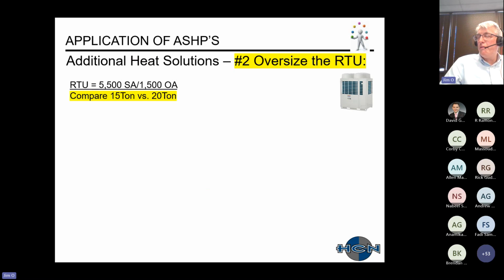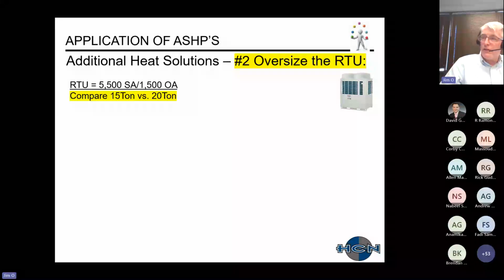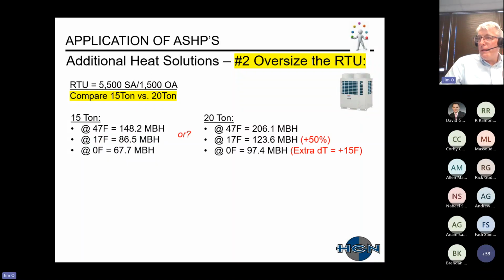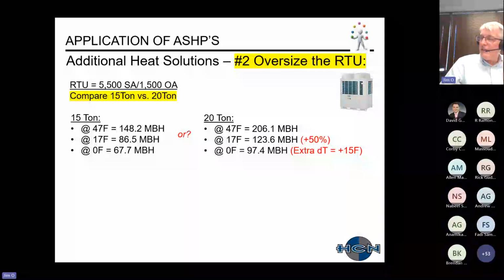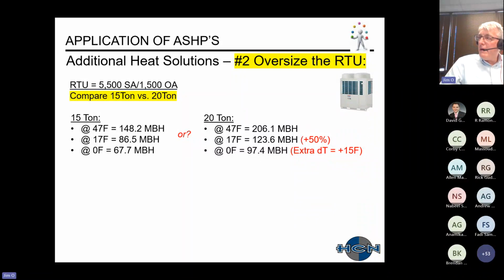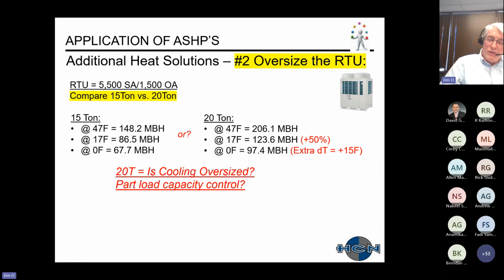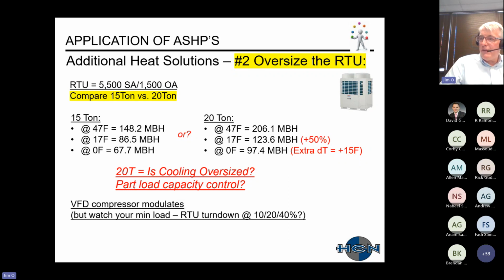Option number 2 is oversizing the rooftop unit, sort of stealing this from the VRF industry. Wanted to compare a 15-ton versus a 20-ton. These are the performance at 15 tons. These are the performance at 20 tons. You can just see at the 17 and 0 degree, we're getting additional heat, a little bit higher temperature. And then want to also compare, just think about, hey, is my cooling load now oversized? With a 20-ton, what's my part load capacity?